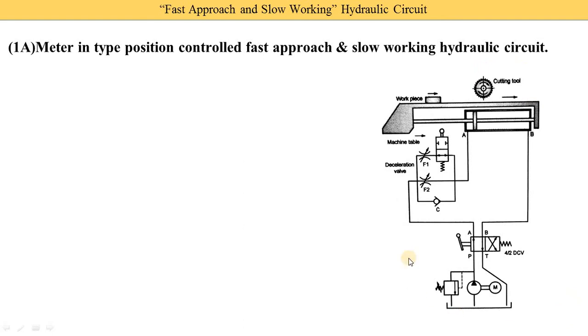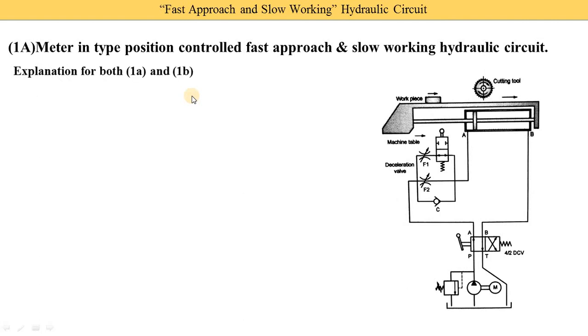Looking at the diagram — why is it called meter-in? Fast approach and slow working is generally required for extension strokes. Meter-in means the deceleration valve assembly — flow control valves F1, F2, and check valve C — is installed at the inlet of the extension stroke. That's why it is called meter-in. In the meter-out type, the same assembly is installed at the outlet of the extension. The A-port is the inlet for extension and the B-port is the outlet.